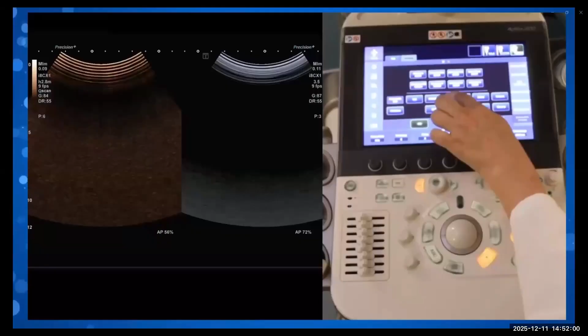Which is a little high. So we have to know on our touchscreen how to adjust this mechanical index. Ideally, you want the mechanical index contrast to be about 0.08 or 0.09. We also have the capability on the console to move between the contrast image and the grayscale image. So we can highlight the grayscale side and adjust the gains there, and then we can highlight the contrast side and adjust the overall gains on the contrast side.